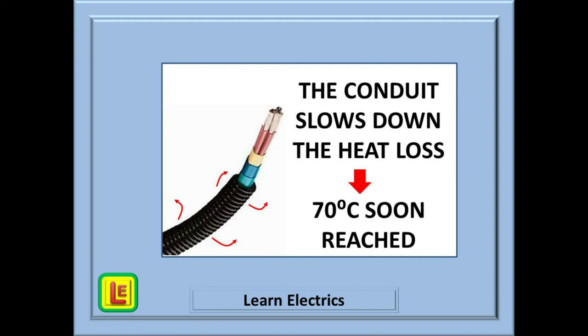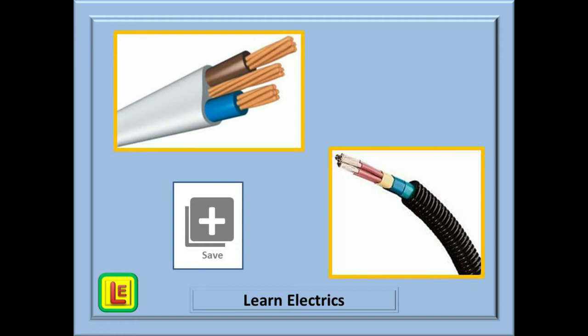For most PVC domestic cables this limit is 70 degrees centigrade, and above this temperature the cable will begin to soften and degrade. Here we have PVC singles installed in plastic conduit. Plastic is a poor conductor of heat. That is why many cooking utensils are made of plastic or at least have plastic handles.